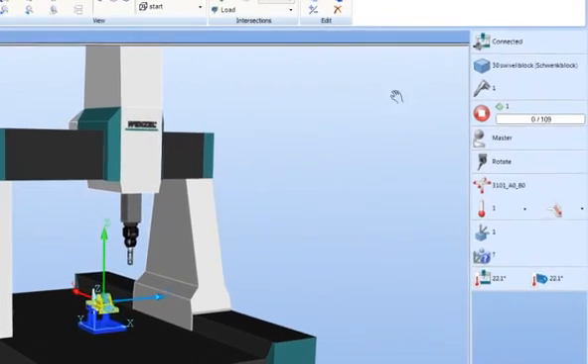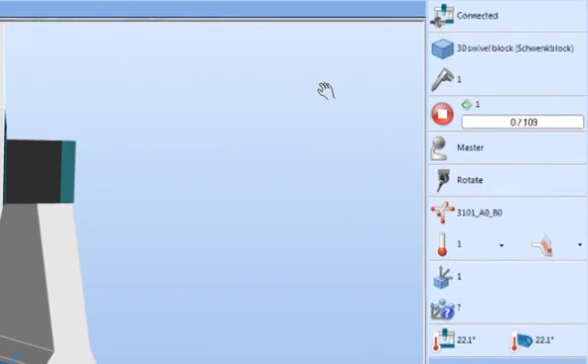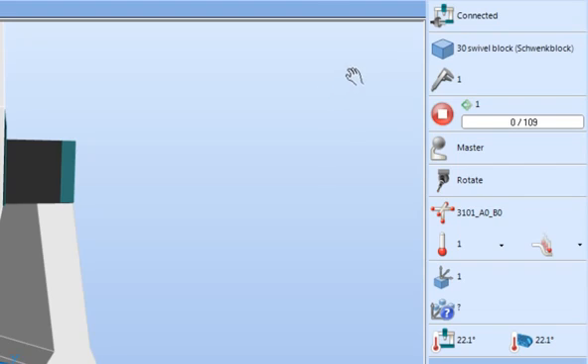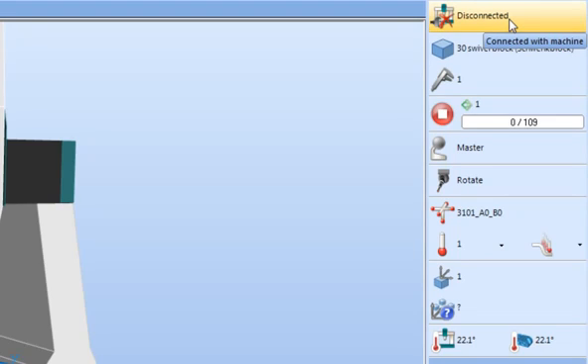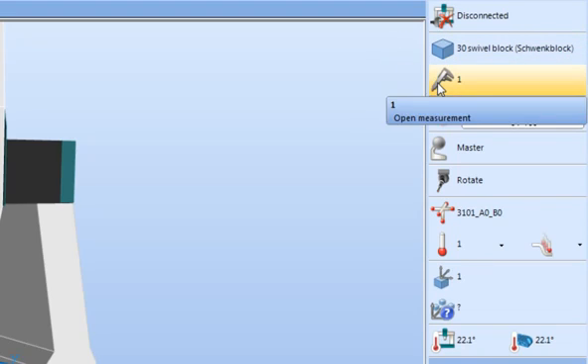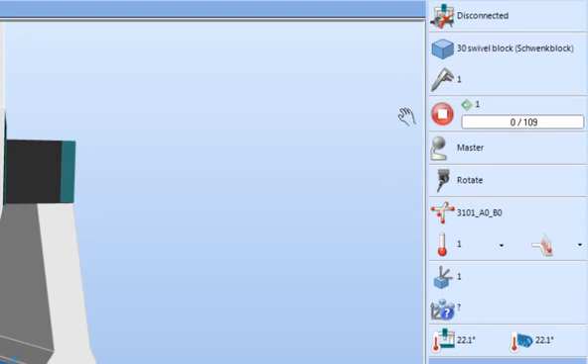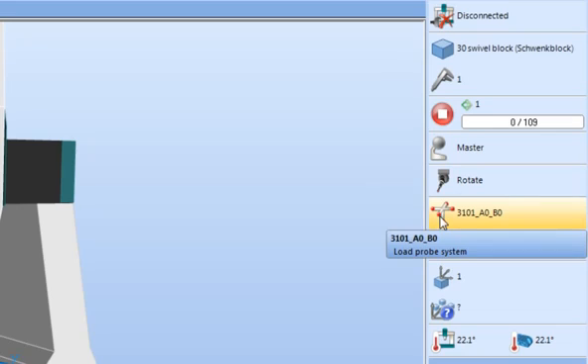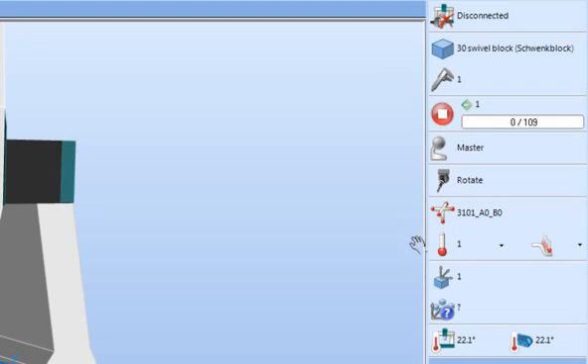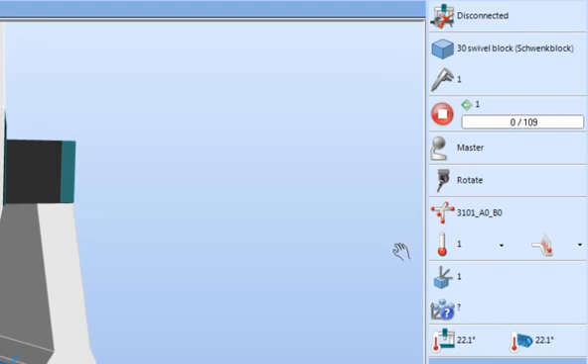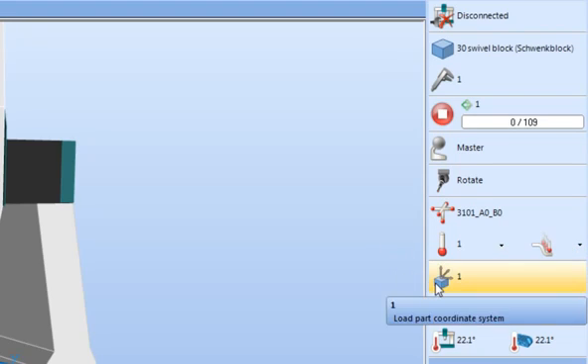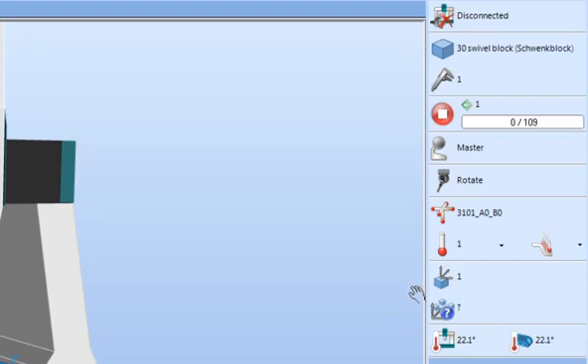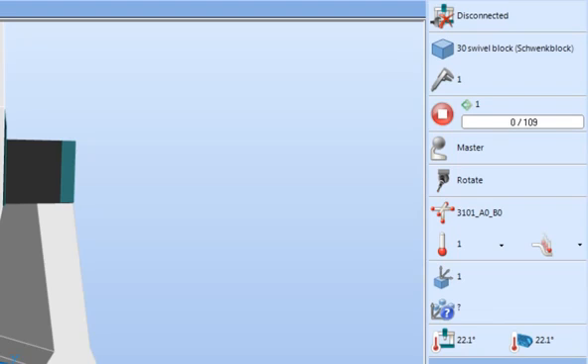The status window shows the current status of all important parameters and aspects of the measurement activity in process. Displayed information includes machine mode—let's switch to offline mode—currently active workspace, currently active measurement, currently active inspection program including status and line number, currently active reference sphere, currently active probe head position, currently active probe system, probe calibration status and whether touch or scan mode is selected, current active part coordinate system and if palette coordinate system is also active, and machine and part temperature if CMM thermal compensation is active. As seen, the status window provides the user at a single glance intuitive knowledge of the measuring system current status.